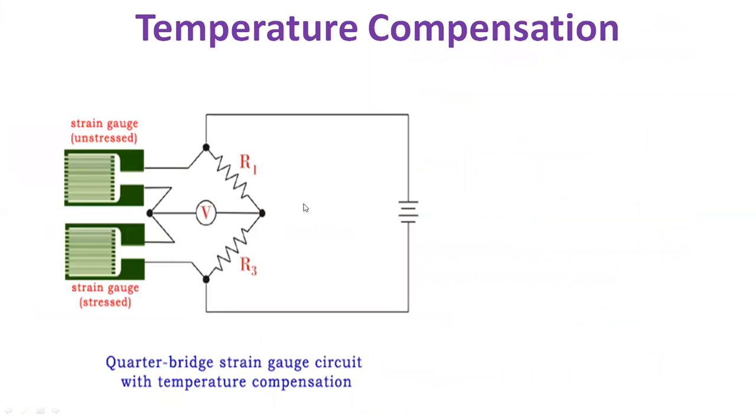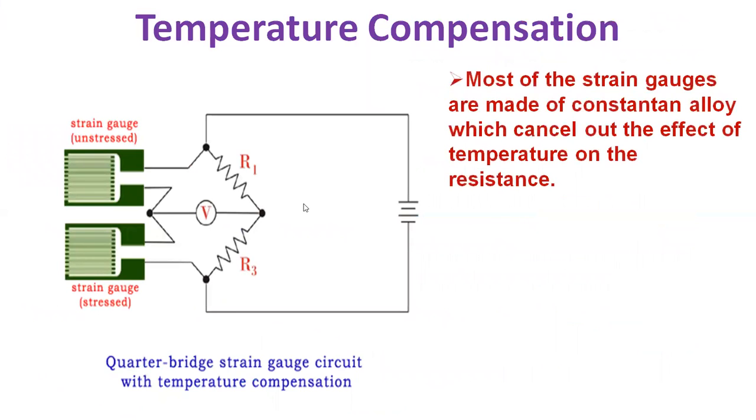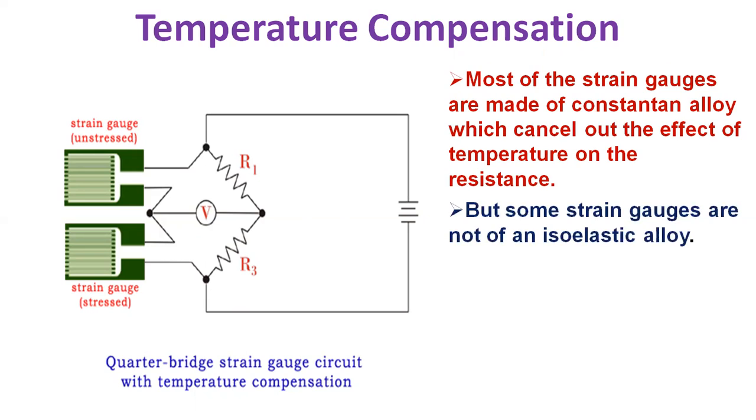Let's see the variation of temperature of strain gauge. We normally require temperature compensation. One factor that affects the resistance of the gauge is temperature — if the temperature is more, resistance will be more, and if the temperature is less, the resistance will be less. This is a common property of all conductors. We can overcome this problem by using strain gauges that are self-temperature compensated or by a dummy strain gauge technique. Most strain gauges are made of constantan alloy, which cancels out the effect of temperature on the resistance. But some strain gauges are not of an isoelastic alloy.